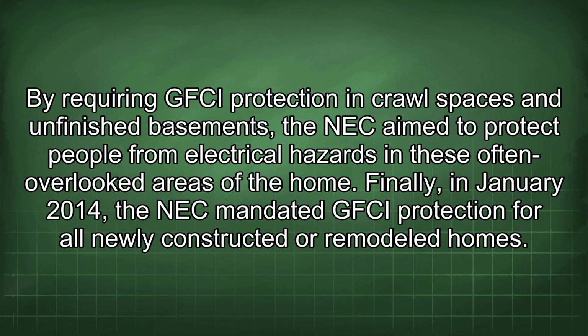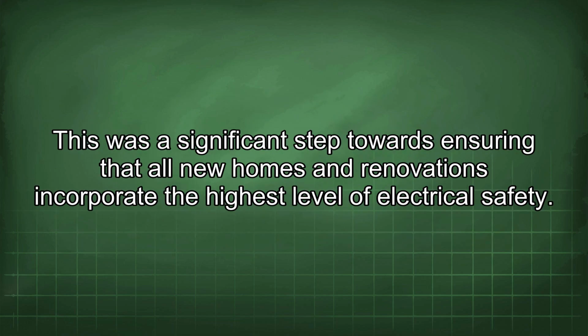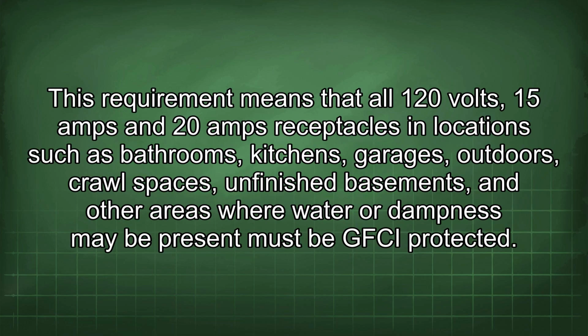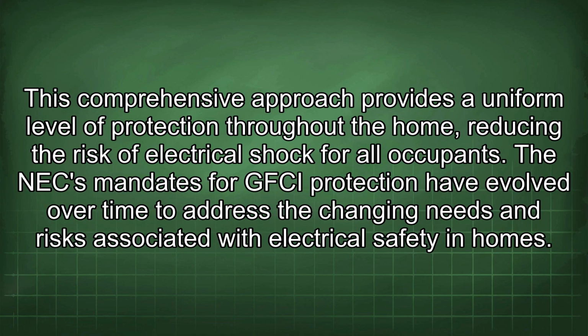Finally, in January 2014, the NEC mandated GFCI protection for all newly constructed or remodeled homes. This was a significant step towards ensuring that all new homes and renovations incorporate the highest level of electrical safety. This requirement means that all 120 volts, 15 amps and 20 amps receptacles in locations such as bathrooms, kitchens, garages, outdoors, crawl spaces, unfinished basements, and other areas where water or dampness may be present must be GFCI protected. This comprehensive approach provides a uniform level of protection throughout the home, reducing the risk of electrical shock for all occupants.